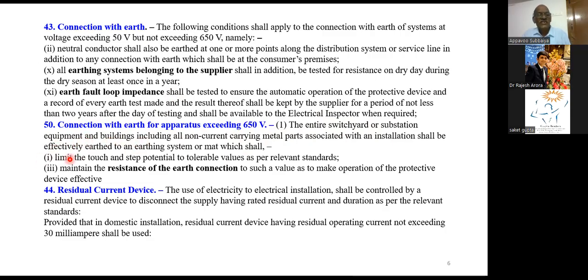So the purpose is to limit the touch and step potential to tolerable values. This is the purpose. Here also maintain the resistance of the earth connection at such a value as to make the operation of the protective device effective. So where the earth electrodes come into the picture, in the supply area and EHV substations, the limitation of touch and step potential is taken into consideration. But these considerations are also there in the LT premises.